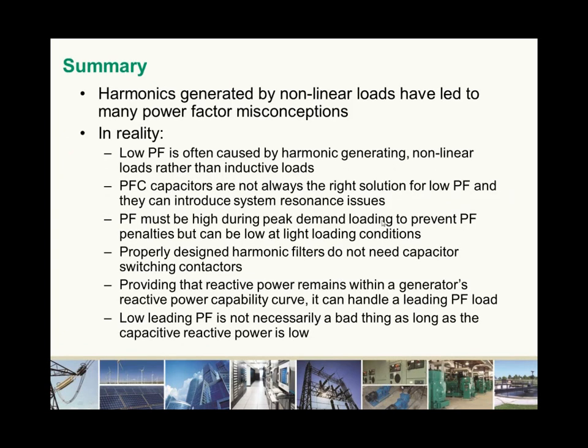So in summary, we now know that harmonics generated by nonlinear loads have led to many power factor misconceptions. In reality, low power factor is often caused by harmonic generating nonlinear loads rather than inductive loads. Power factor correction capacitors are not always the right solution for low power factor, and they can introduce system resonance issues. Power factor must be high during peak demand loading to prevent power factor penalties, but can be low at light loading conditions.